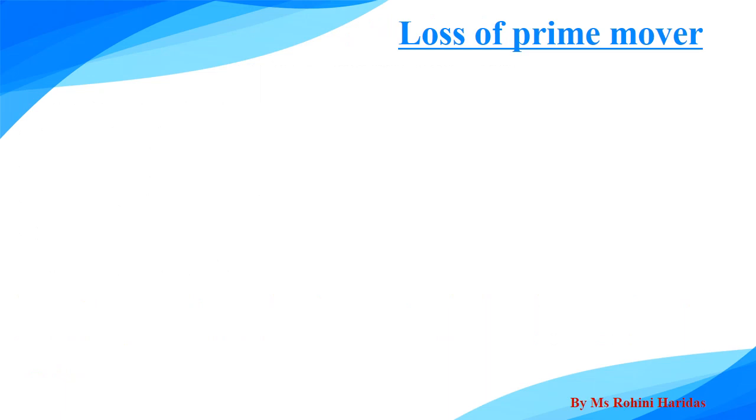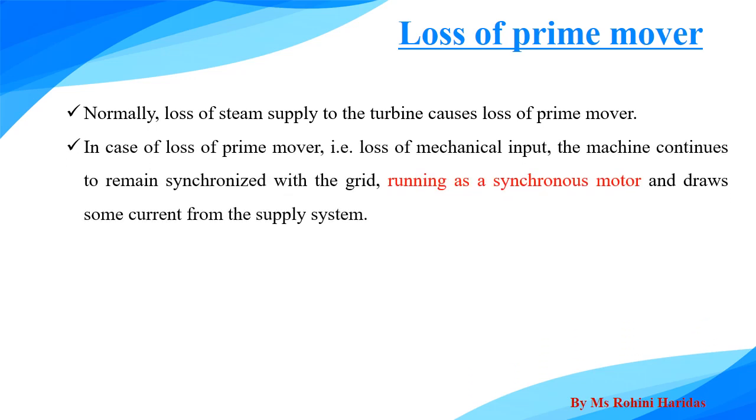Another abnormal condition is the loss of prime mover. Normally, the loss of steam supply to the turbine causes the loss of prime mover. In case of loss of prime mover, that is the loss of mechanical input, the machine continues to remain synchronized with the grid, running as a synchronous motor and draws some current from the supply system.